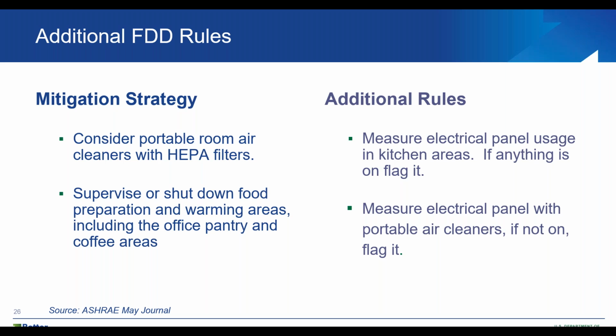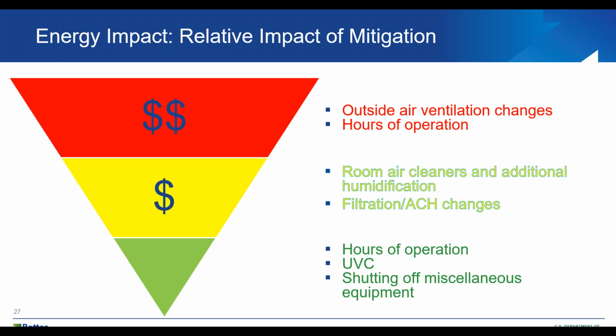Okay, next slide, please. So I'm not giving specific dollars, but just kind of a relative perspective on energy impact and how your changes may impact the energy consumption in the building. Clearly, if you're running equipment a lot more hours and using a lot more outside air, it's going to be using a lot more money because you have to heat it, you have to cool it, and you're running the fan energy. It's very noticeable in environments that are not temperate. In an environment like California, where the temperatures are more moderate, you could probably bring in a lot more outside air.